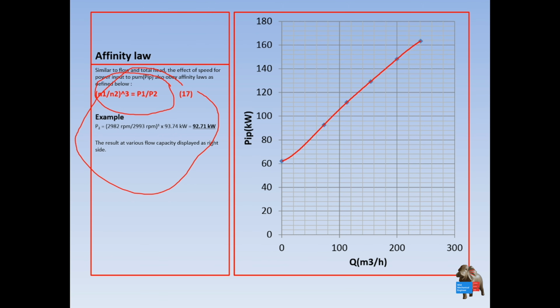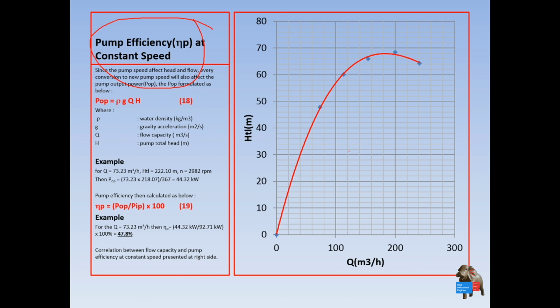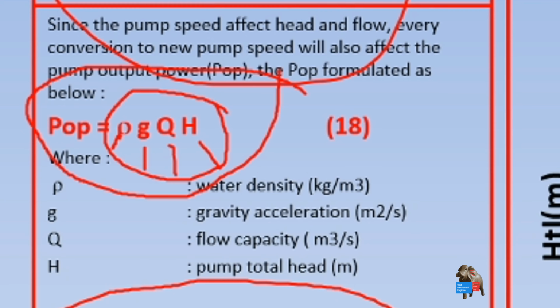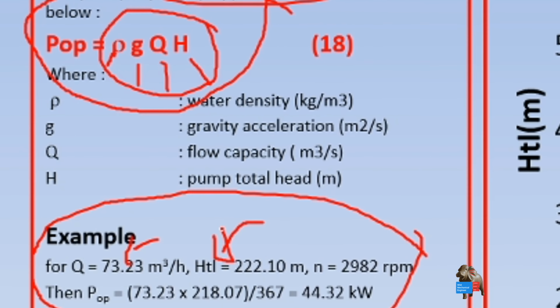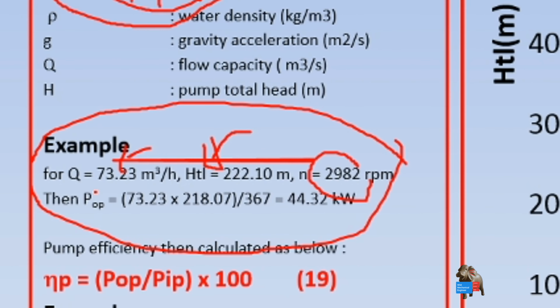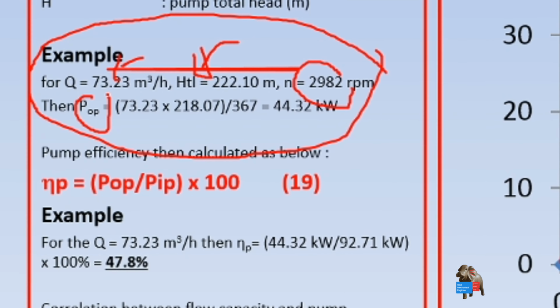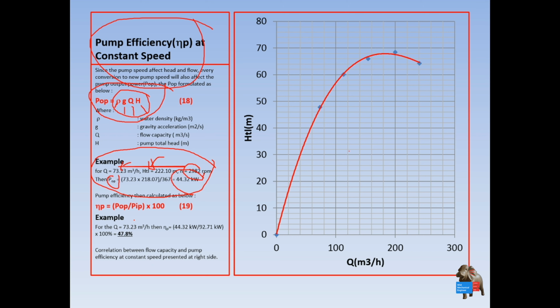Okay, and the pump efficiency is calculated like this. The power output of the pump, we call it hydraulic power, is calculated based on this: the specific weight of water, density, gravity, flow capacity, and the total head. This is the example for the flow capacity. You have this total head at this RPM, then you have the power output of the pump. And what is the power input to the pump?